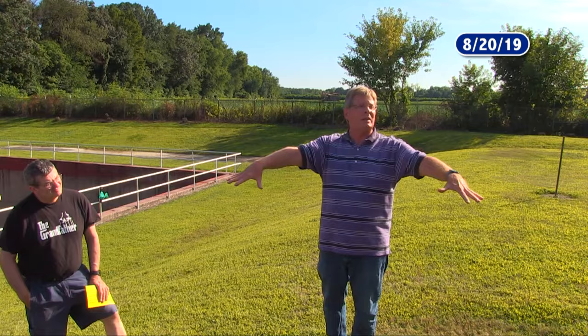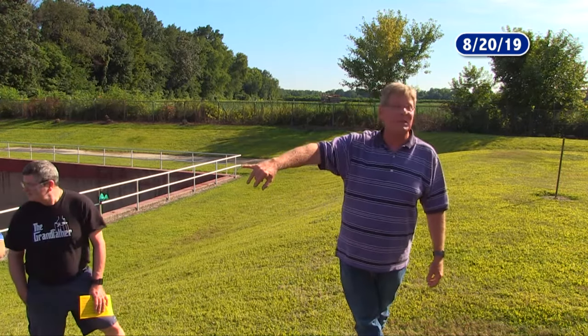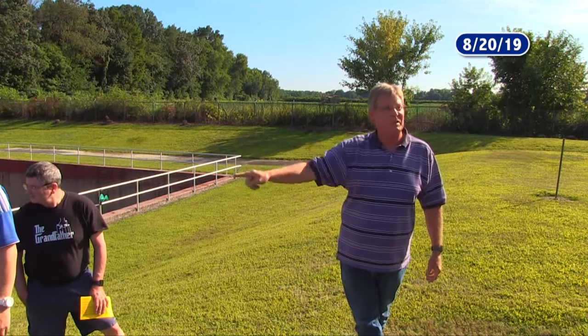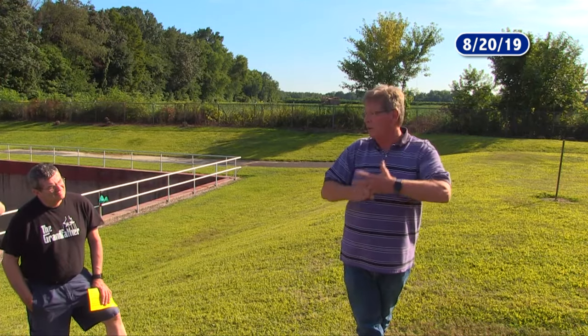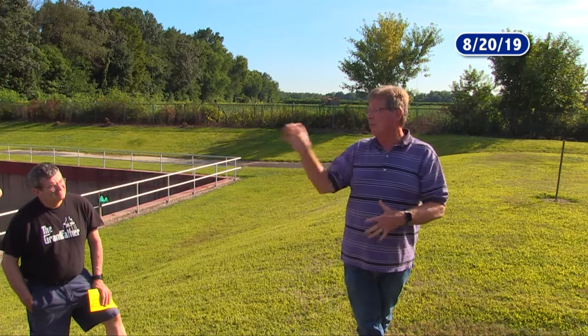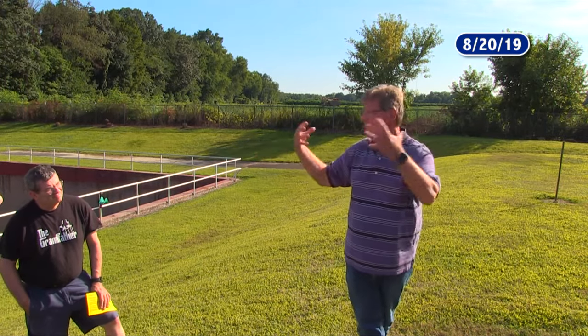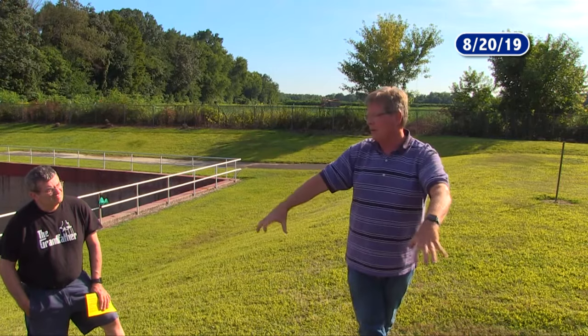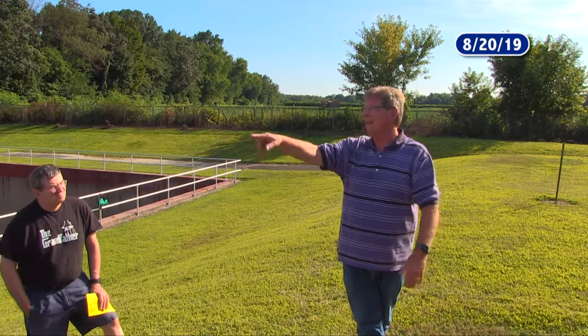And so by cycling little by little, that is starting to dissipate some because it's not being whipped up so much all the time. But as you can see, even an hour on, an hour off, and we're talking since the beginning of this month, that's how much is still floating on top of that tank. And it's a lot. So a full Headworks with rag removal, grit and grease separation and removal would prevent that. You would have clarity right now. All you would see is clear water as the biologics in that have settled. Right now they're denitrifying. You wouldn't see any of that at all. And you wouldn't see any rags hanging on any of these tethers.